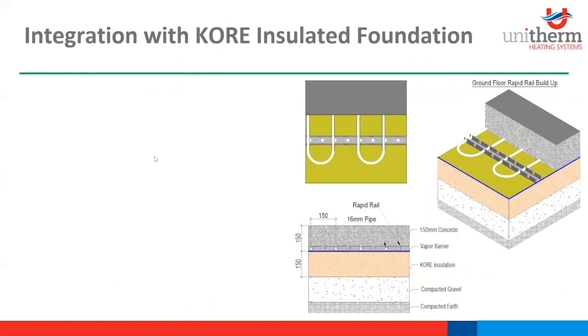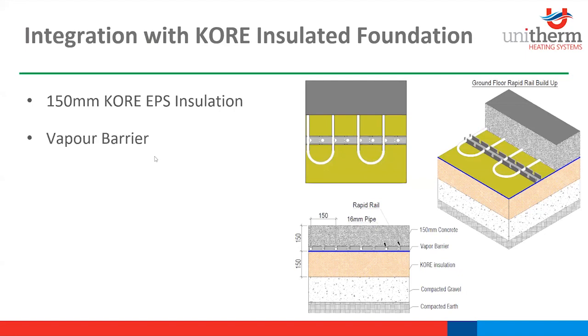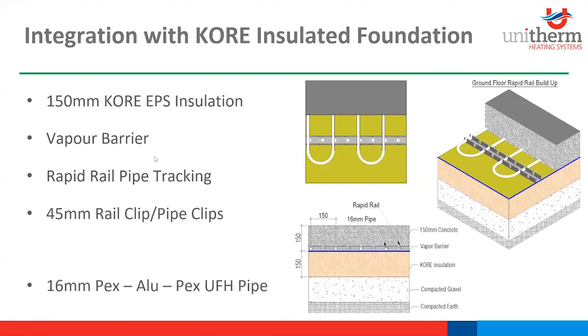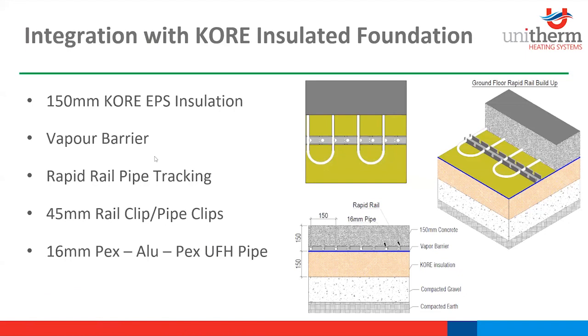So just going to look through the build-up of KORE's insulated concrete foundation here and how we utilize it with underfloor heating. As Andrew said, maybe 200 mil of T3 compacted gravel or compacted stone. This is all leveled out. Then you have your KORE insulation. We'll just take it as 150 mil KORE, 150 mil insulation, vapor barrier, rapid rail track, and this is to house your underfloor heating pipe, just so you can get the proper centers throughout the house and even heat distribution. Then there are clips for the railing, and then we have a 16 mil PEX alu PEX, or there's a PEX alu PERT as well, which is easier to work with. And these are all clipped down as well. Then we have 150 mil reinforced concrete, so the pipes are in that.